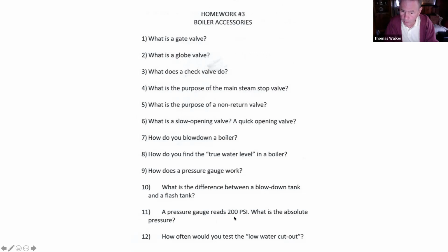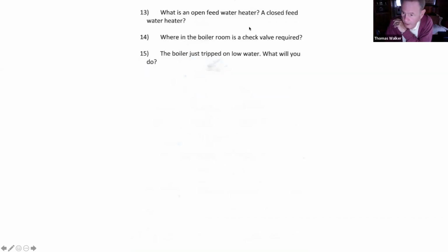A pressure gauge reads 200 PSI. What is the absolute pressure? 214.7. There you go. 214.7 what? PSIA. PSIA, absolutely. All right. How often would you test the low water cutout? Once a shift at least. Once a shift. And the answer they're looking for is at the start of every shift you work. All right. Everybody knows what an open and a closed feed water heater is. We just covered that seconds ago. All right. Where in the boiler room is a check valve required? Between the feed water pump and the boiler. Between the feed pump and the boiler.